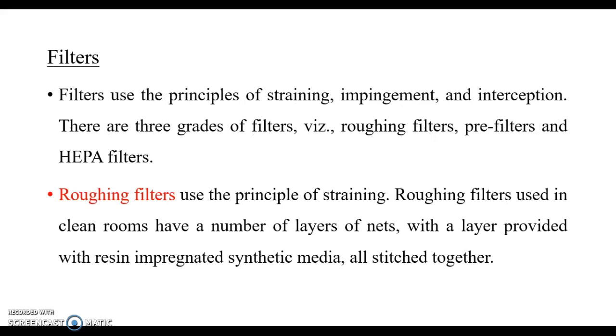Next, the filters. Filters use the principle of straining, impingement and interception. Filters filter the air. There are three grades of filters in the refrigeration system: roughing filter, pre-filter, and HEPA filter. The roughing filter uses the principle of straining, and it has a number of layers of net with a layer provided with a resin impregnated synthetic medium. All the layers are stitched together.